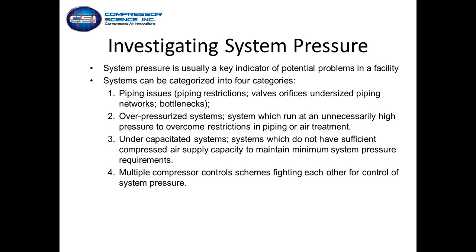That's an extreme example, but those are the type of examples that we've seen in people overpressurizing systems. Undercapacitated systems: some customers have gotten to the point where production has brought in a new piece of equipment, an airline was hooked up to it, and maintenance doesn't necessarily even know that it's been installed, or they know it's there but have no idea how much air it was actually going to consume. So you end up with a 50 horsepower compressor that's now running in drawdown because the system's undercapacitated. So you're having pressure problems because when they run that machine, or one of the two machines, it draws the system pressure down to a point of critical failure.